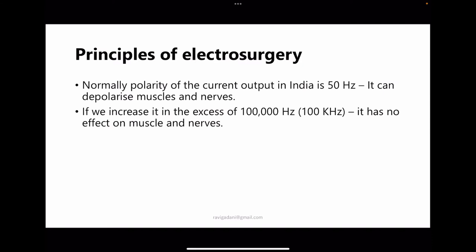If we increase the frequency from 50 Hz to around 100,000 Hz, it has no effect on muscle or nerves — and that is the principle we use. The electrosurgical unit takes current from the wall outlet at 50 Hz and converts it to a frequency of 350,000 to 500,000 Hz (500 kHz). This is also the frequency of AM radio, which is why it is also known as radio frequency.